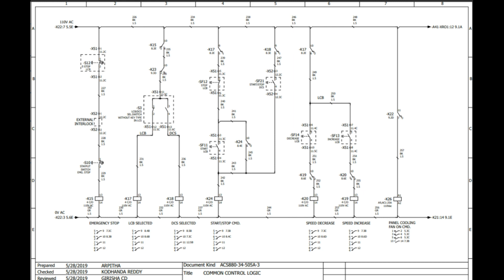Generally K23 is healthy, let's suppose, and we'll see what K23 is in the next page. And 110 volt has come to the selector switch button. This dotted box you can see on the left hand side is LCB, and on the right hand side it is DCS. So this will decide from which mode the drive will run, from local mode or from the PLC mode.